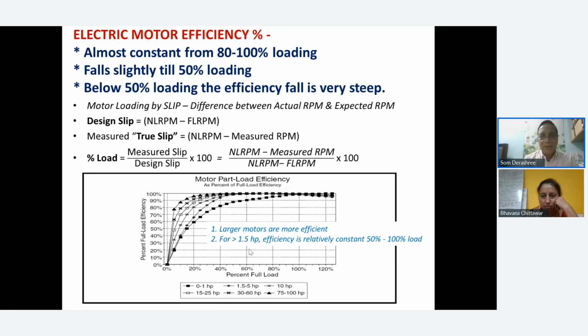And to know the loading of the motor, many times your nameplates are not available. So what you do is use a tachometer. You find out the design slip with the full load RPM, and for no load you can even take the synchronous speed. So synchronous speed minus the measured RPM, divided by synchronous speed minus the full load RPM, gives you the percentage loading.